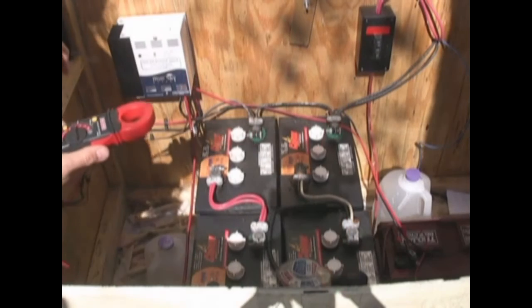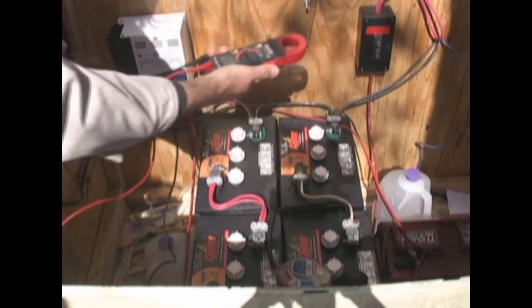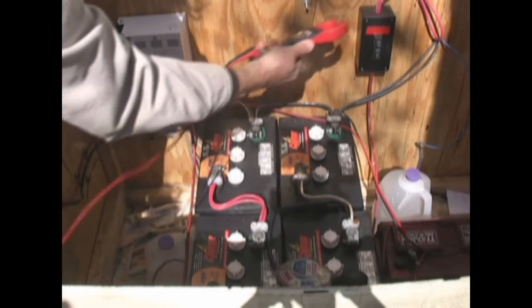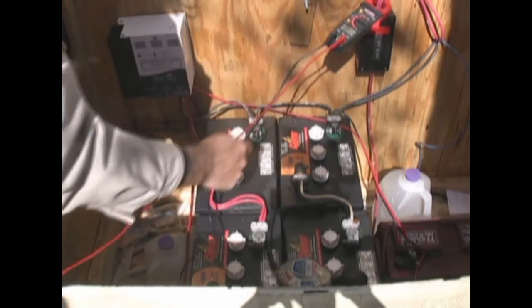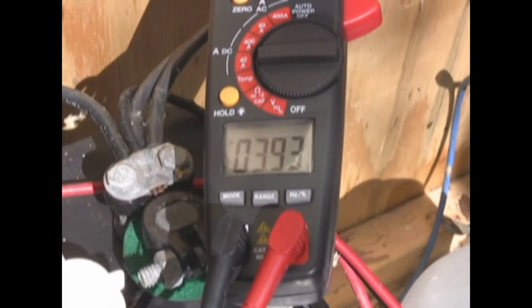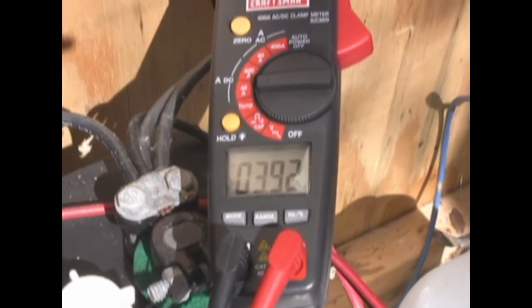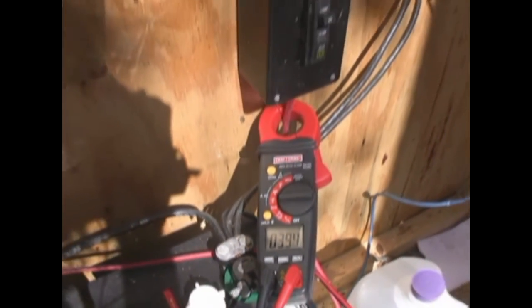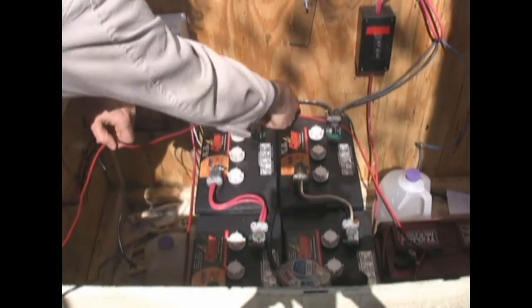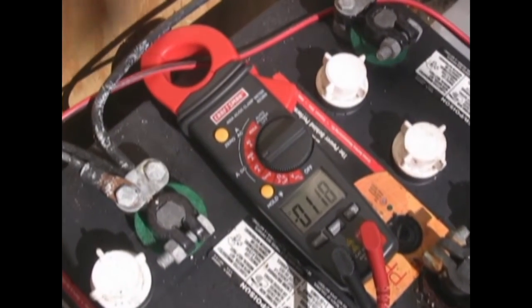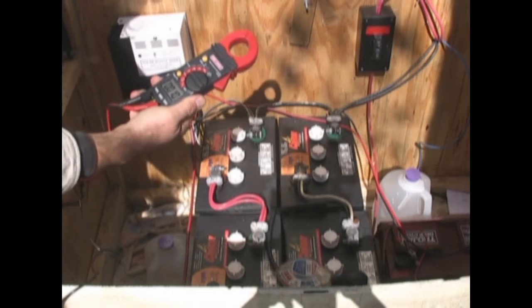Or I can go to our output breaker and say, how much power is going into the house? Just clamp it right around the positive leads going out, and take a look at the metering on that too. So anywhere you've got a positive wire run, like this auxiliary battery bank that's trickle charging, I can pop it around that positive wire and get a reading of how much power is going over there without having to break the circuit. That's what's great about these clamp-on meters.